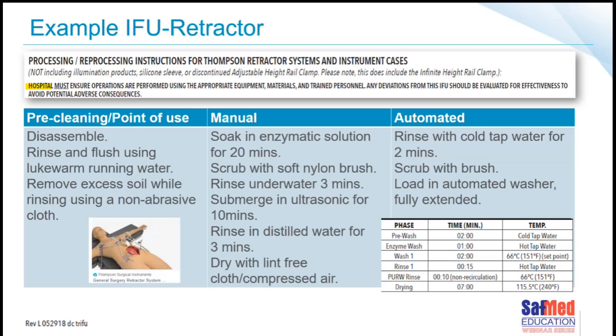In their guidelines, they talk about point of use or pre-cleaning, and they say the following: we must disassemble the device. It goes into a bit more detail, but I've just summarized it for today. You need to rinse and flush using lukewarm running water. Whilst you are doing that, you remove the excess soil using a non-abrasive cloth. Not a brush at this point, a cloth, and not just running water.